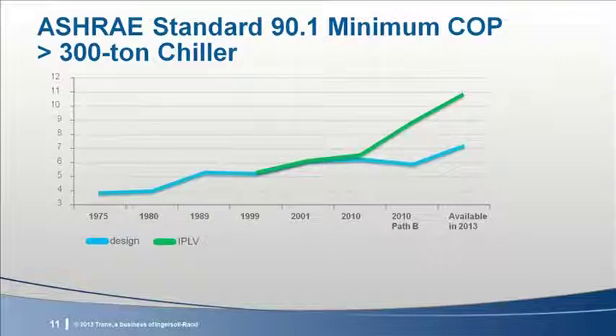Now, here's a historic graphic that shows the increase in ASHRAE 90.1 minimum chiller efficiency in terms of coefficient of performance, or COP. The two lines represent full load COP at AHRI standard conditions and the integrated part load value, or IPLV. Integrated part load value was first required by 90.1, 1999, so until that time, it's not plotted. Now, the difference in the 2010 Path B requirement is due to the IPLV rating points at 75% load and below having reduced entering condenser water temperatures. Later, we'll cover the effect that assumption has on a chiller with a drive.